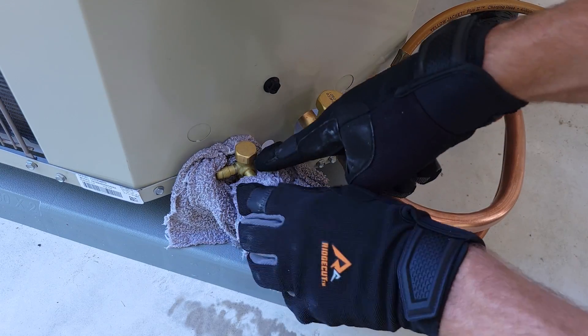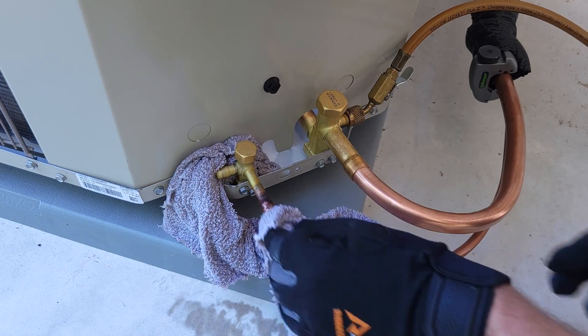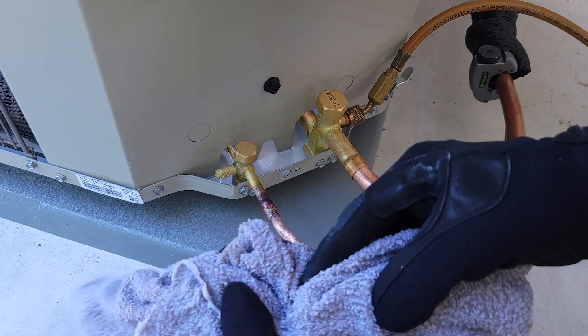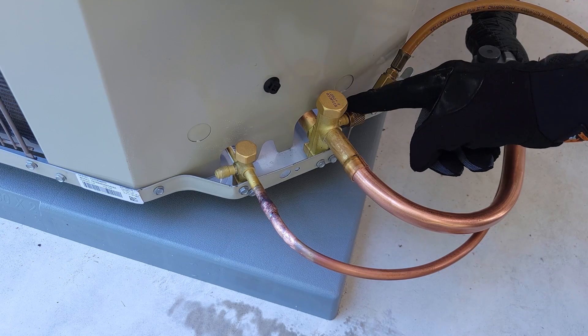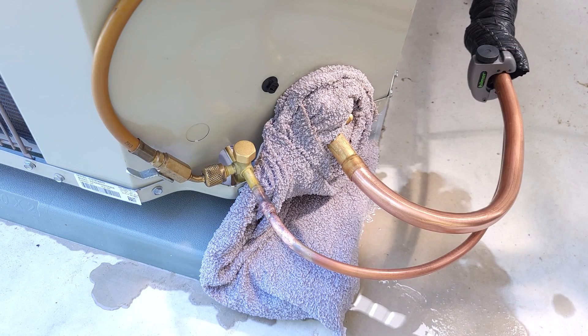We want to avoid heating up this valve because there's an O-ring inside — you don't want to melt that. I'm going to re-wet this rag with cold water and then switch this nitrogen hose over to the other side. We put our rag over the service valve and switch the nitrogen. I also turned the nitrogen flow up just a little bit higher so the ball rises a little bit more.